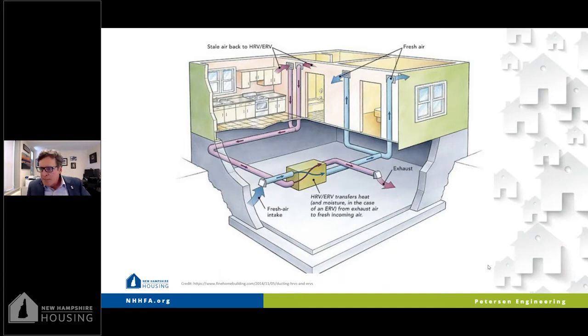The other thing to note about the ventilation approach here is that it's decoupled, separate from the heating and cooling system. The fundamental reason for that and benefit of that is that the need for ventilation is continuous. So we typically run ventilation systems in our projects 24/7, 365. There's no interface with the occupant. The expectation is that the space benefits from ventilation continuously, and there's no time when it doesn't benefit from ventilation.